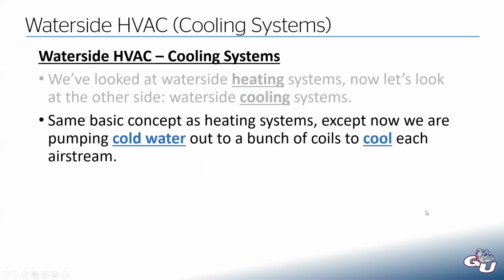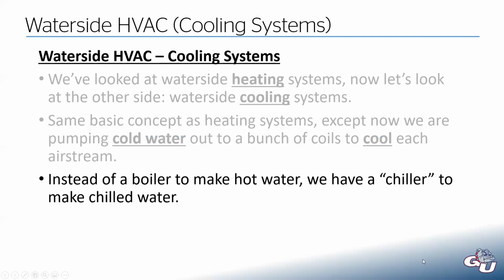Same basic idea. We're still pumping water out into our building, out to a bunch of coils that we use to condition our air in the building, except now instead of using hot water, we're using cold water that is going to cool a bunch of air streams throughout the building, as opposed to heat them. Instead of a boiler, which we use to make hot water, now we're going to have what's called a chiller. And I've mentioned chillers several times in this class so far, but up until now, you might not have really known what I meant by that term.